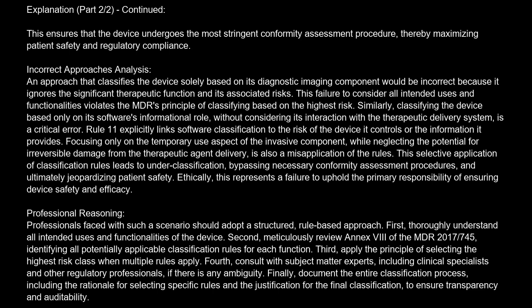Rule 11 explicitly links software classification to the risk of the device it controls or the information it provides. Focusing only on the temporary use aspect of the invasive component, while neglecting the potential for irreversible damage from the therapeutic agent delivery, is also a misapplication of the rules. The selective application of classification rules leads to underclassification, bypassing necessary conformity assessment procedures, and ultimately jeopardizing patient safety. Ethically, this represents a failure to uphold the primary responsibility of ensuring device safety and efficacy.